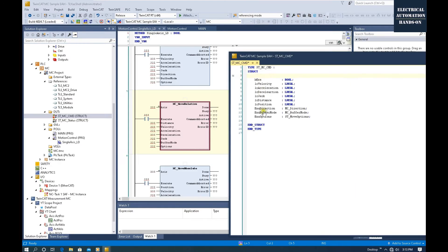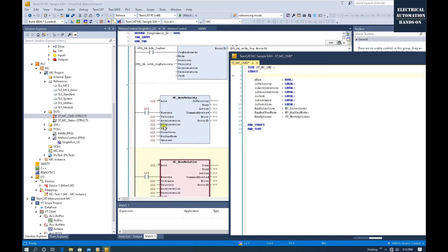We create tags between the STRUCT and the END_STRUCT here. I created all those variables within this structure. For each function block or motion type, it has: execute, velocity, acceleration, deceleration, jerk, distance, and position. Keep in mind, for direction, buffer mode, and options — they are all enumerator structures. That's why the prefix of these variables is named 'enu'. All those structures come from the system — for example, MC_BufferMode comes from the TwinCAT structure.